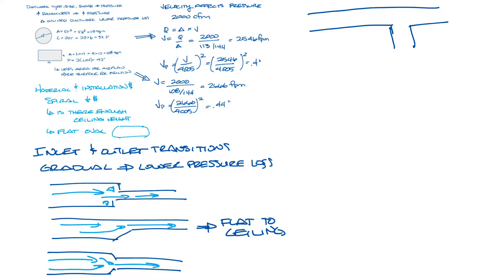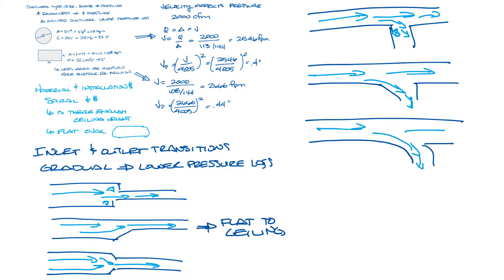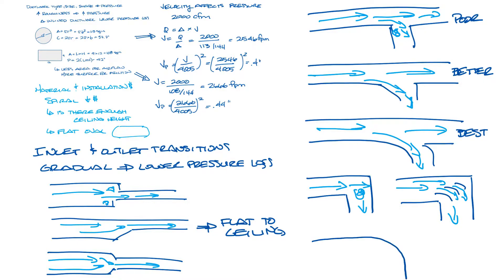Same thing if you have to tap off on your ductwork. An abrupt 90 degrees will give you a lot of turbulence and will be poor from a standpoint of pressure loss. It would be better if you could transition like this middle one, and best if you could do a soft transition completely. For elbows, a hard 90 will be your worst option because there will be a lot of turbulence and pressure drop. Your next best option would be to put in turning vanes that would guide the air through the transition, and then your best option would be to have a soft 90.